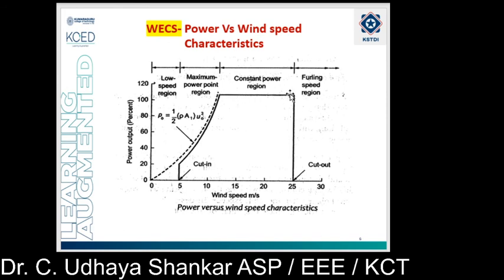The third region is the constant power region. During high wind speeds — above about 12 meters per second — the rotor speed is limited to an upper permissible value based on the design limits of the system components. In this region, the power coefficient is lower than CP max. Large machines use pitch control to maintain turbine speed as constant — such a machine is known as pitch regulated. Classical European machines use fixed blades with constant speeds, and the blade twist and thickness are designed to crudely maintain speed as constant — such a machine is known as stall regulated. This is a simple system requiring only passive stall, with no moving blade surfaces or complicated hardware. However, power capture is somewhat less due to rounding of the power curve in the case of stall regulation.